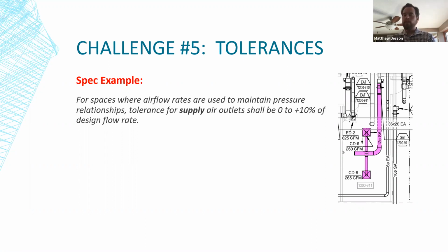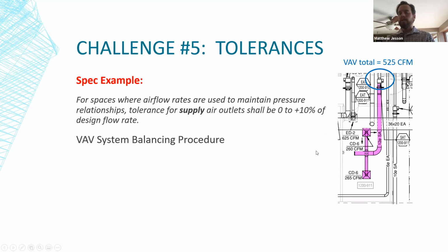So the issue with this, as far as the accuracy of the instrument goes, it's not too bad. But what kind of system do you have and how does it operate? In this case, you've got a VAV system. And this VAV serves this room for a total of 525 CFM. So let's talk about how we balance this.